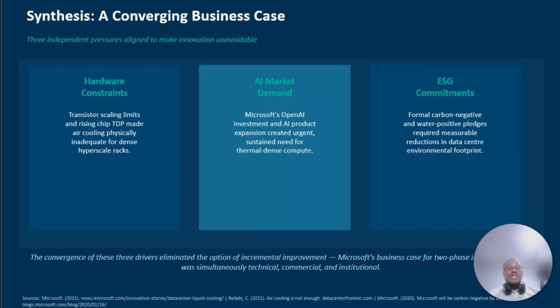So let's bring this all together. Three independent pressures - hardware constraints, AI market demand, and ESG obligations - converge at the same moment. Here's the key insight: each driver alone was manageable, but together they made doing nothing more expensive. Air cooling couldn't handle the heat, conventional expansion couldn't meet AI demand fast enough, and incremental improvement couldn't satisfy sustainability norms. Two-phase immersion cooling solved all three simultaneously, which is exactly why Microsoft deployed it at production scale in 2021.